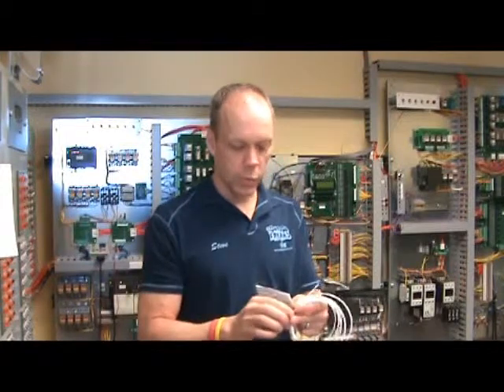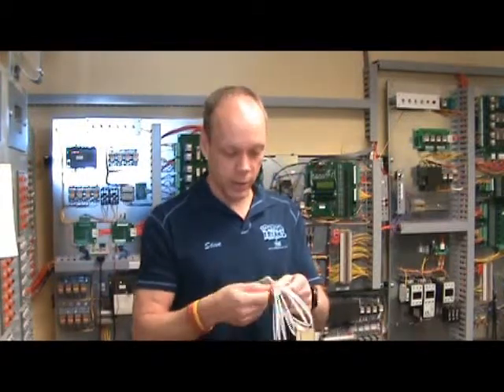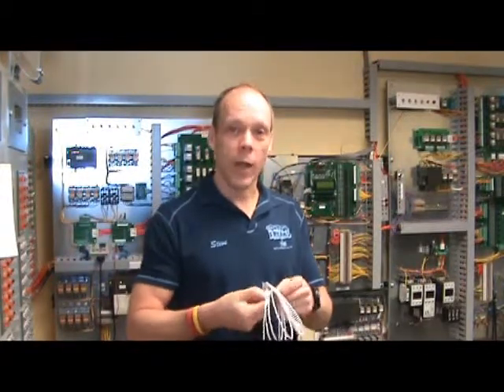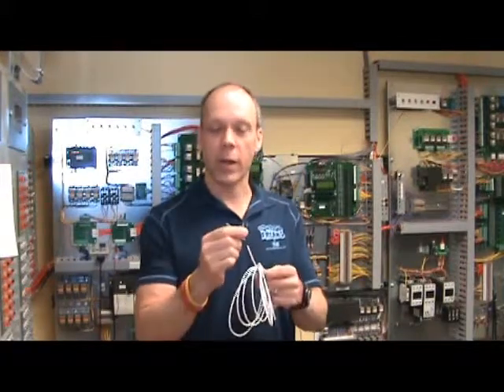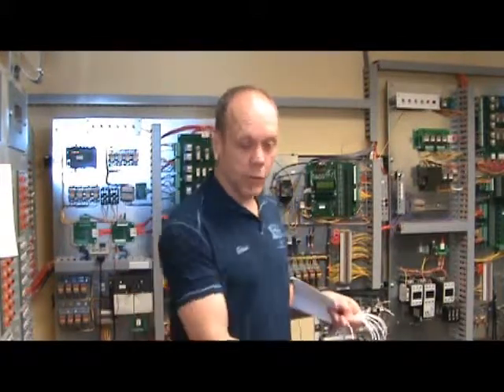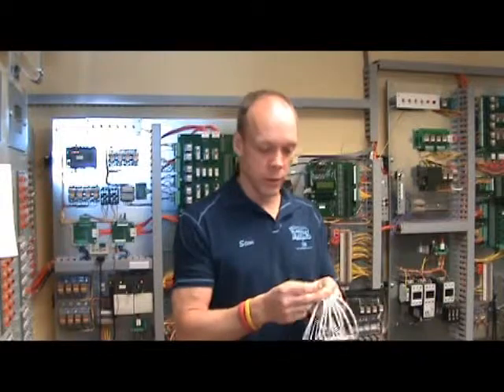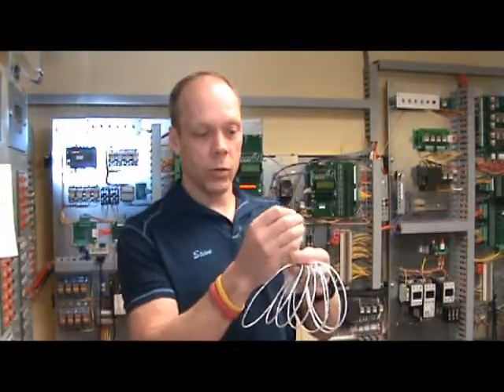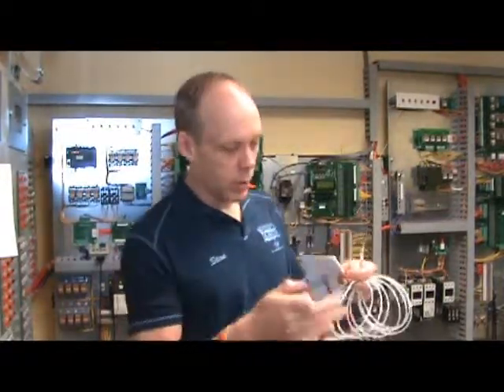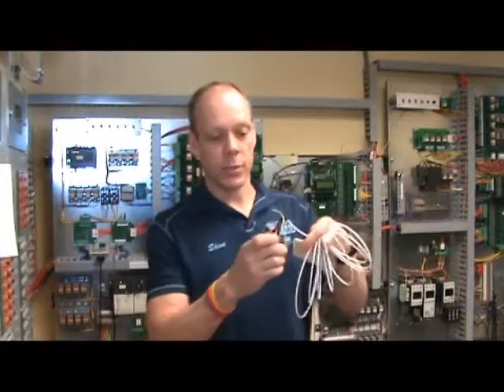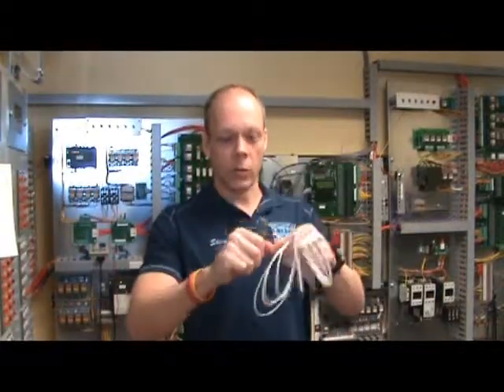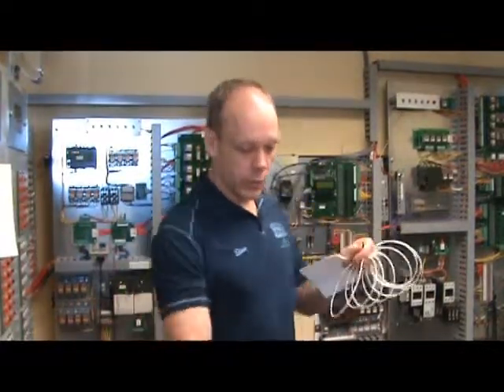Inside that bag you're going to get a temperature sensor with approximately 12 feet of cable on it. If for some reason you have to add cable to it, you can wire it right onto it, and that's not a problem. It's not going to affect the temperature reading at all. This is a shielded cable with 2 wires on it. Take a clipper and just clip the shielding off. We're not going to need that, and we don't want to have any short circuits, so we're just going to get rid of that.